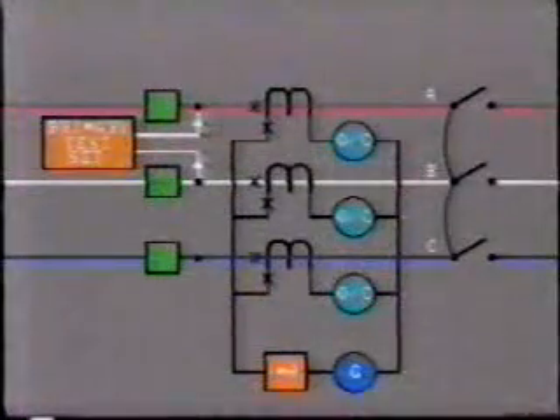The next test is to ensure that the CTs are connected the right way around, that is, they are in balance. For this test, a temporary short circuit is placed across the primary conductors. In this particular example, test current is passed through the A phase CT primary conductor, and then back through the B phase CT in the opposite direction. The resultant CT secondary currents should cancel each other out. If the CT connections are correct, the residual current, which is being measured by the milliammeter, should be 0.